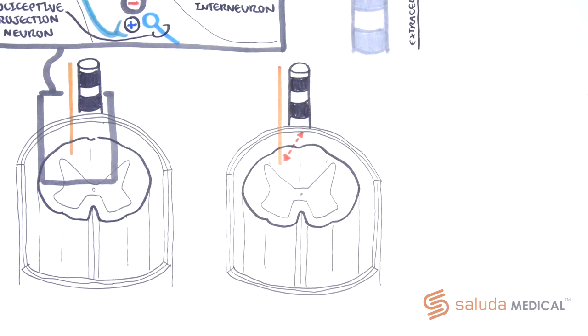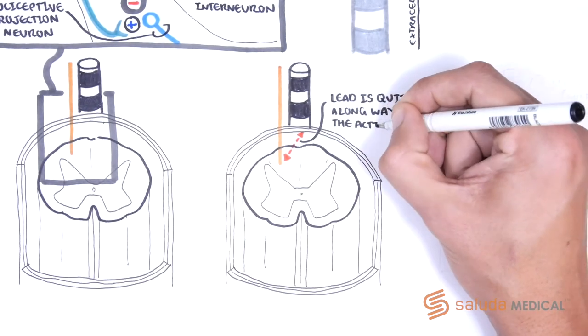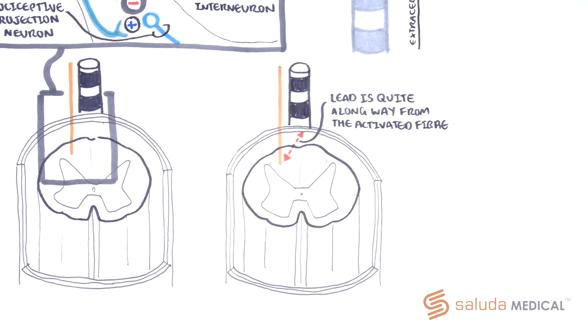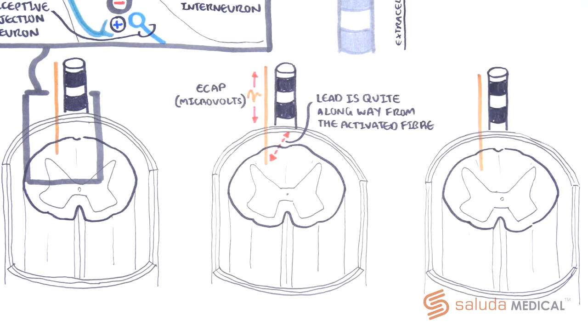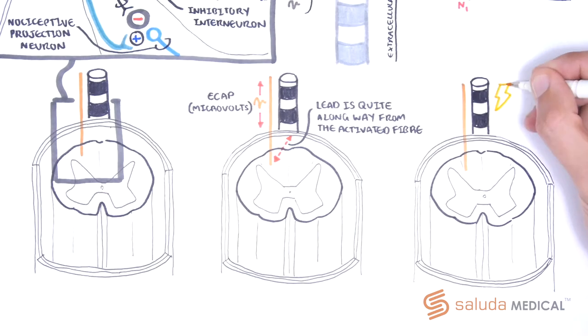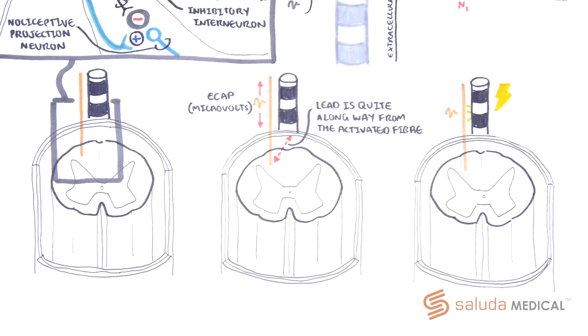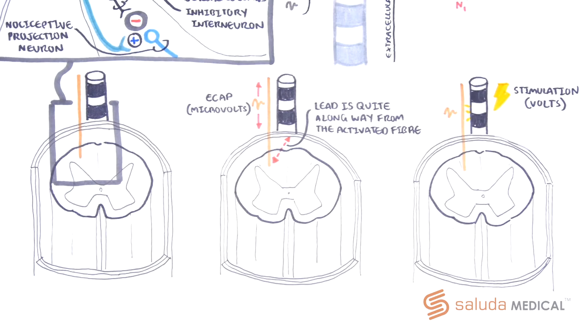As the lead is quite a long way from the activated fibers on a cellular scale, the size of the recorded response is small and measured in microvolts, one microvolt being one millionth of a volt. Whereas the stimulus applied to generate these ECAPs is in the order of volts, which is six orders of magnitude larger, just fractions of a second before the recording. To put the difficulty of being able to achieve such a recording into perspective, that is like you trying to listen to this video while Formula 1 cars pass by you.